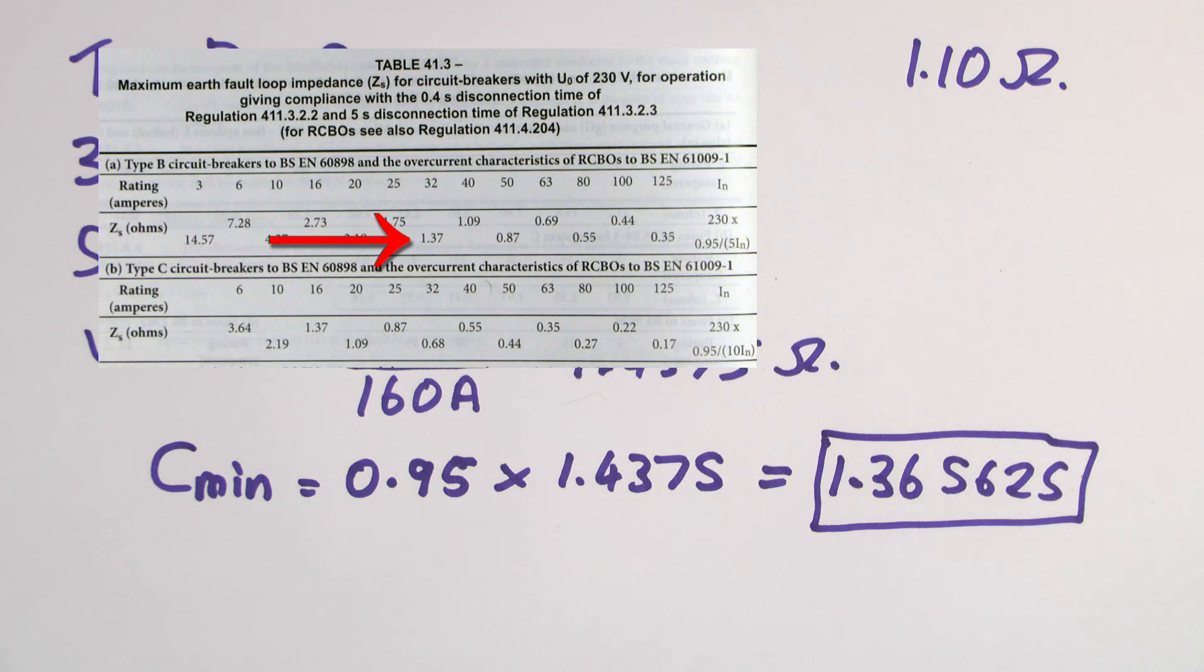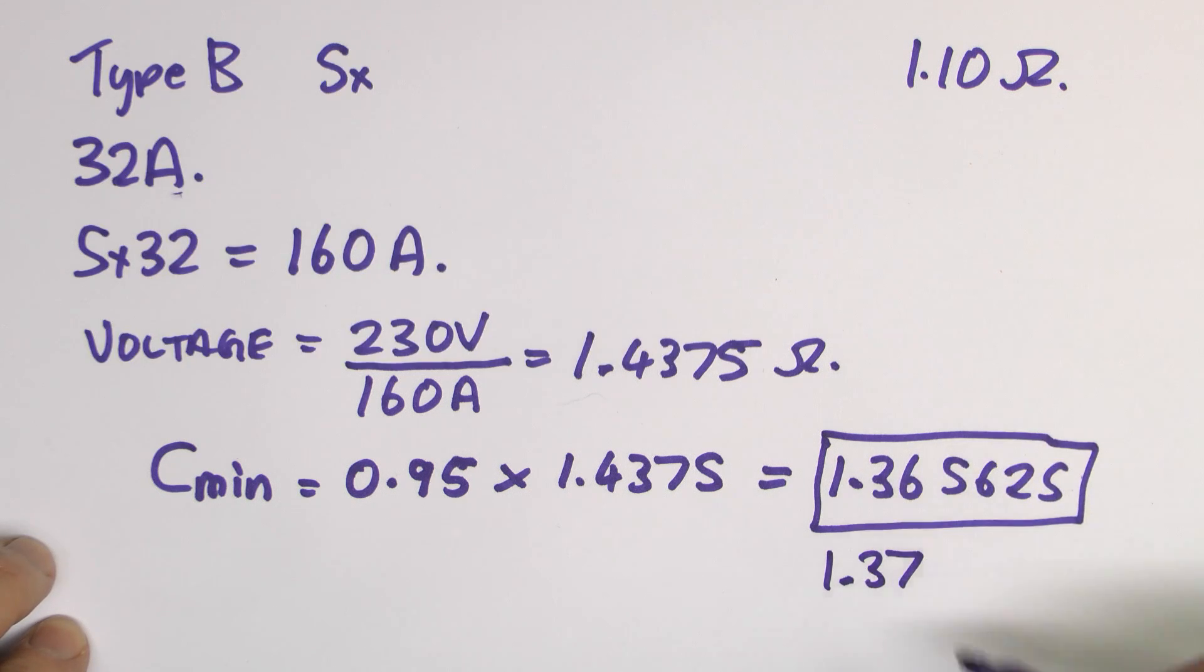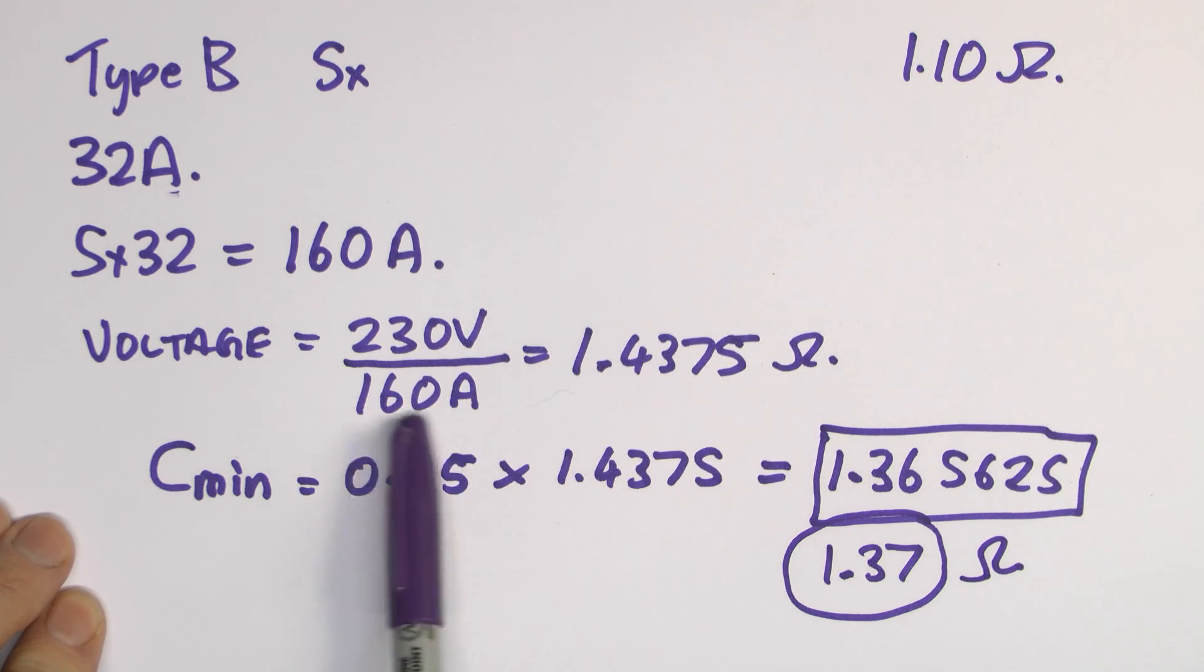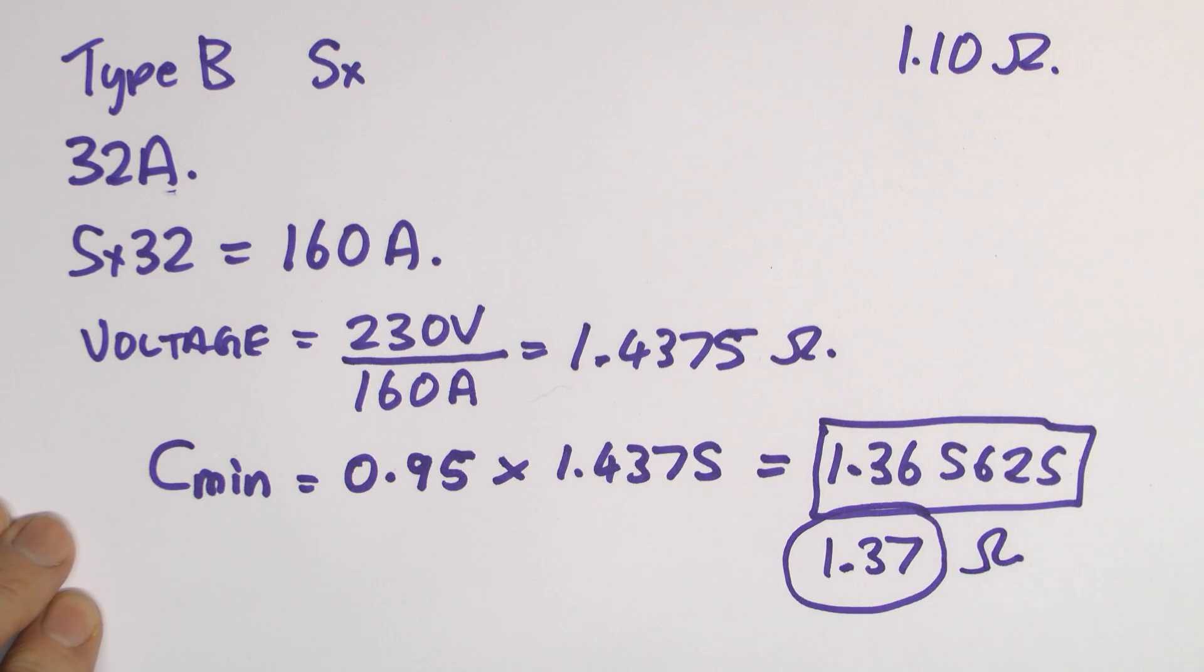And the value we get from that is 1.365625 but we don't really care about all of those digits. So this here is really our result from the calculations. So all we're doing is type B gives us five times. We know it's a 32 amp device so 160 amps is the current we need. Resistance or impedance for that is voltage divided by the current. So 230 volts divided by 160 gives us 1.4375. And then we're going to apply this correction factor of Cmin, which is just basically to allow the fact that the voltage could be less than 230 volts in some cases. And we get 1.365625. Now if we have a look in that table 41.3, we can see the value it's got in there is 1.37. And that's basically what we've got here because all that is is we're just rounding up to the two decimal places. And that gives you the value of loop impedance that you'll be looking for. And again, this is the maximum value because of course if this value is lower, then it means that the current you're getting is actually considerably more than this.